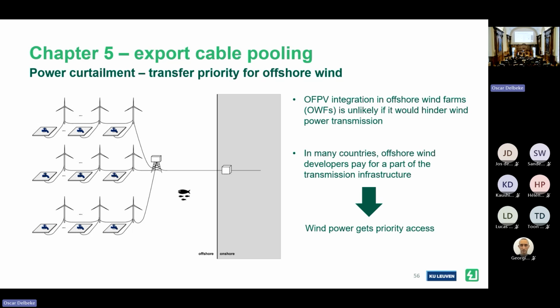Power curtailment avoids that cables are overloaded and overheated. And I make the very conscious decision that if power needs to be limited, first I curtail solar power and only then wind power, because the wind power was there first. Solar power is very unlikely to be integrated if it would hinder the transfer of wind power. So when curtailment needs to happen, I curtail solar power first and only then wind power.